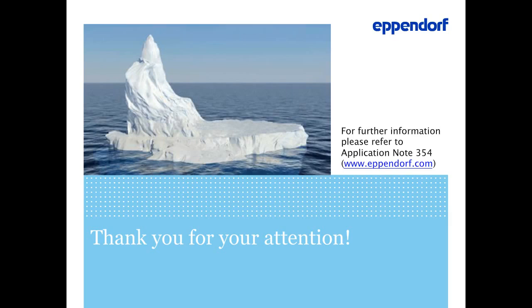Yeah, that's a good question. So when talking about tip batches, as I said in the presentation, I do recommend to calibrate every new tip batch when using alternative tips. Regarding the system itself, meaning also the pipette, it belongs a little bit to your work.